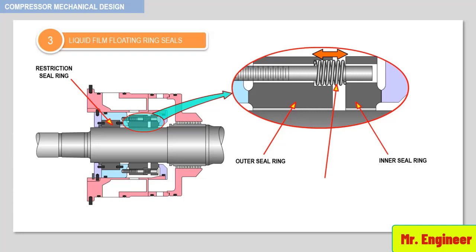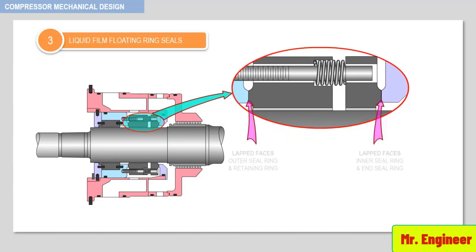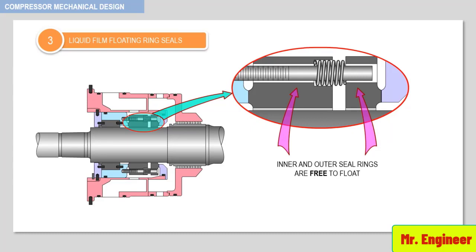The inner and outer seal rings are held apart by compression springs. This maintains the lapped faces of the inner and outer seal rings in contact with the end seal plate and retaining ring, respectively. The inner and outer seal rings are free to float, and are therefore called floating rings, free to align radially to accommodate any shaft vibrations, as depicted in this simplified animation.